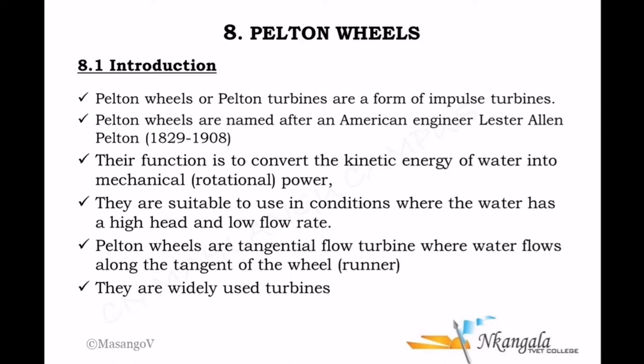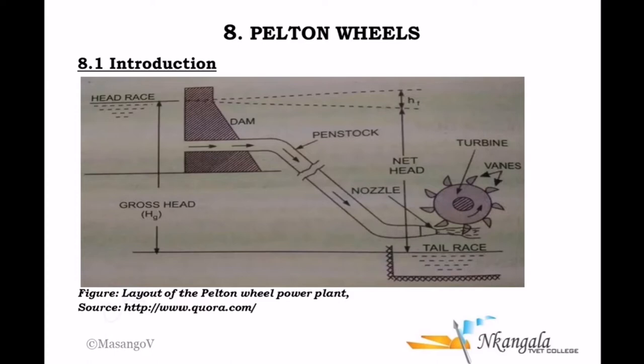Pelton wheels are therefore suitable to use in conditions where the water has a high head — that high head represents high potential energy and low flow rate. They are tangential flow turbines where the water jet is tangential to the radius of the wheel, also called the runner. They are a widely used form of turbines. Water situated at an upper area is drawn to the bottom, generating kinetic energy from the potential energy.